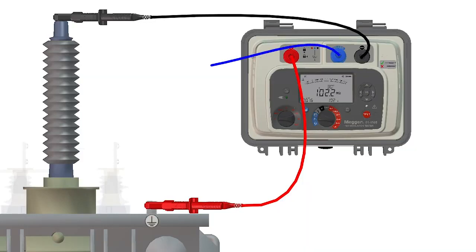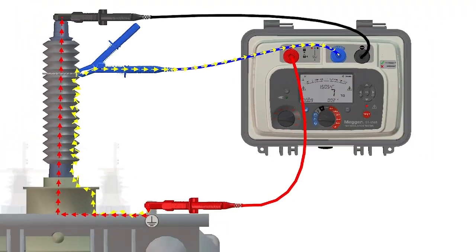When the guard terminal is added, shown here as the blue test lead connected to the asset, the surface leakage current is removed from the test result, providing an accurate measurement of the material's insulation.